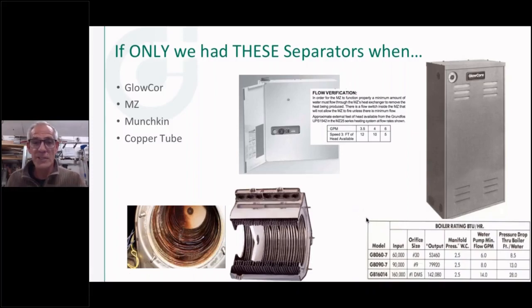Because of the wide open sections, we were trying to pipe these boilers that may be a replacement, took out a cast iron boiler, put one of these in, left the same pump there, thought we could get away with it, and we got rewarded with what you see in this picture over here on the left: heat exchangers that would burn through. They would overheat, they would pop, they would bang, they would flash to steam, and eventually, and you can see in this picture, there's actually a couple pinholes squirting water up in the center of those, where those tubes are burned black.